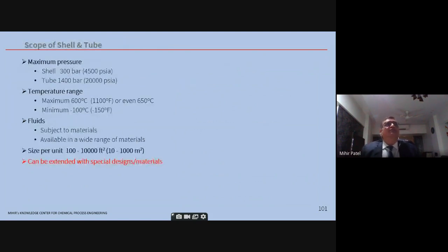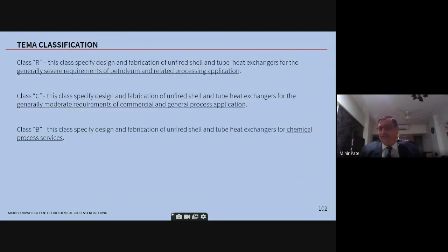Scope of shell and tube. So maximum pressure, temperature range has been specified here. You can exceed this also depending on the specific requirements, but these are the normal ranges one can comply with. TEMA classification. So there are 3 TEMA classifications. TEMA is basically Tubular Exchanger Manufacturers Association. So class R is for refinery services. These are very stringent. Class C is for general process application. For example, you may have, let's say, a compressor having a lube oil cooler. So there you can go with a class C. Class B is for general chemical process services. Okay. So class R is the most stringent among these.